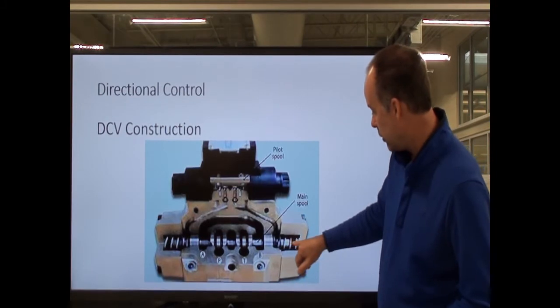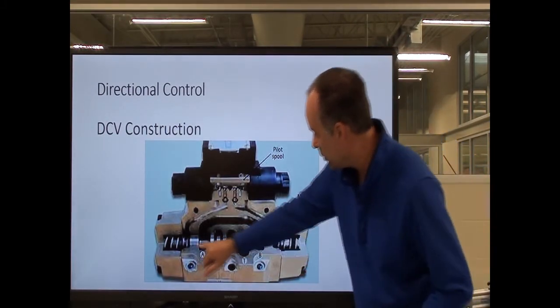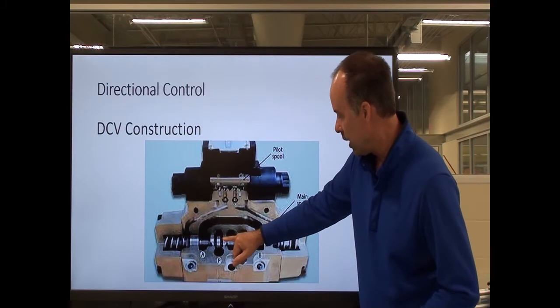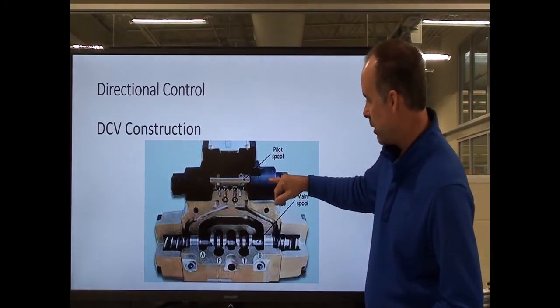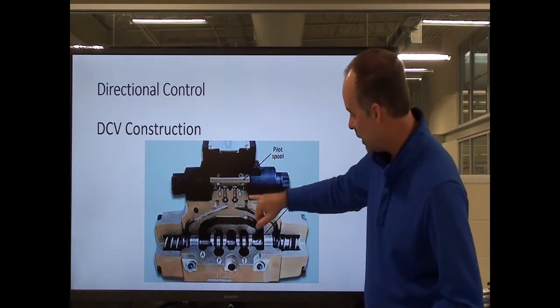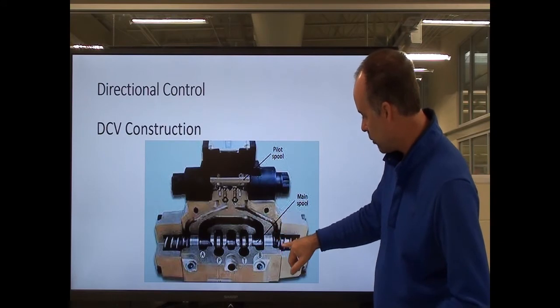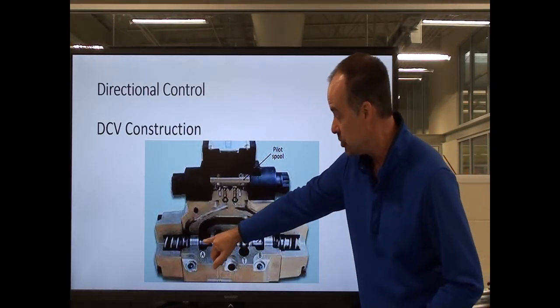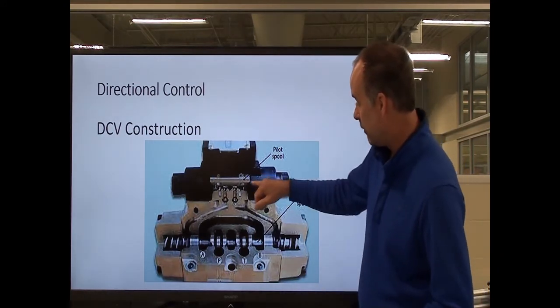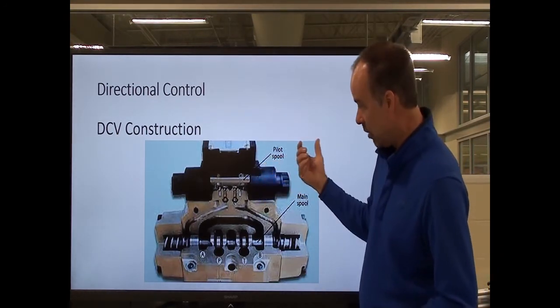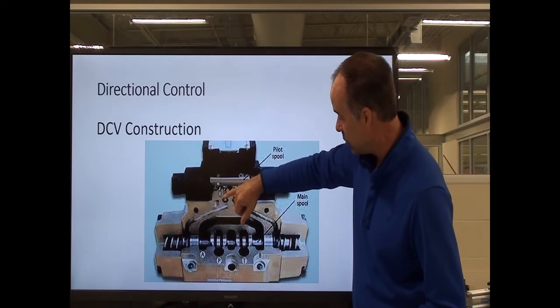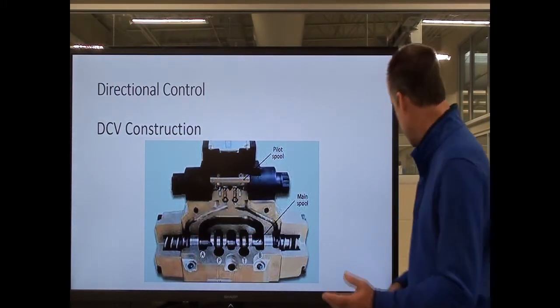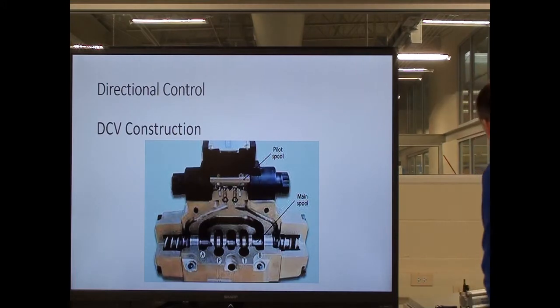On the end of the spool you can see springs on each end — these springs hold the spool right in the middle. When I actuate the pilot valve up top, it puts hydraulic pressure on the end of the spool and causes it to physically move and shift to one side. If I want it to go the other way, I can energize the other side of the spool and pressurize that side to shift it over.